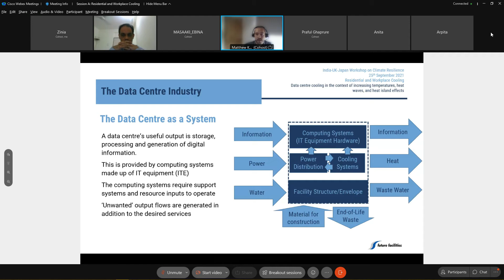The industry has tended to stay a step ahead of regulators through self-driven initiatives. ASHRAE, the American Society of Heating, Refrigeration and Air Conditioning Engineers, published guidelines for thermal conditions in data centers, which are very widely used to determine the operating point of data center cooling systems. Over the years, they've continuously adjusted these in collaboration with IT equipment manufacturers, typically widening the limits for temperature and humidity to help data center operators use less energy and water.